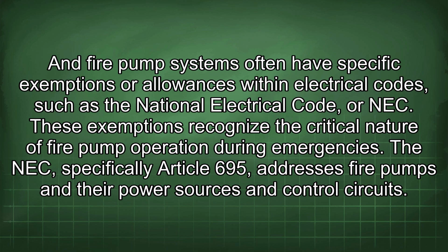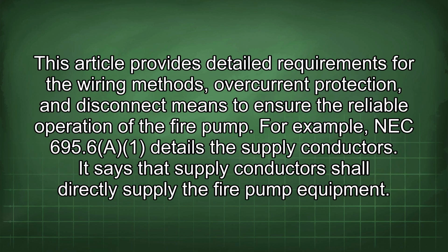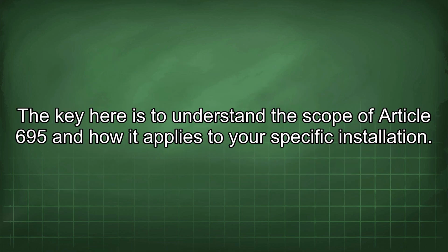The NEC, specifically Article 695, addresses fire pumps and their power sources and control circuits. This article provides detailed requirements for the wiring methods, overcurrent protection, and disconnect means to ensure the reliable operation of the fire pump. For example, NEC 695.6 details the supply conductors. It says that supply conductors shall directly supply the fire pump equipment. The key here is to understand the scope of Article 695 and how it applies to your specific installation.